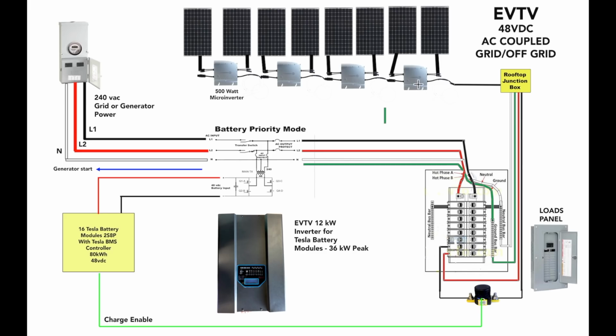Now, the way this is supposed to work is that your grid input, the microinverters have to have that to produce a waveform and an output. They simply shut down without it. They have to have something to sync to. And this is an anti-islanding provision required by Underwriters Laboratory 1741, which the utilities are all about, because they don't want, in theory, your solar installation to power the grid when the grid's down, because it might injure a maintenance person.